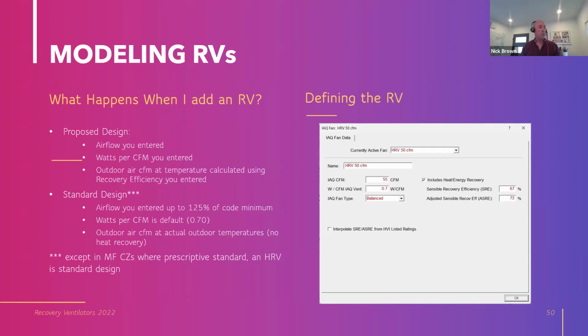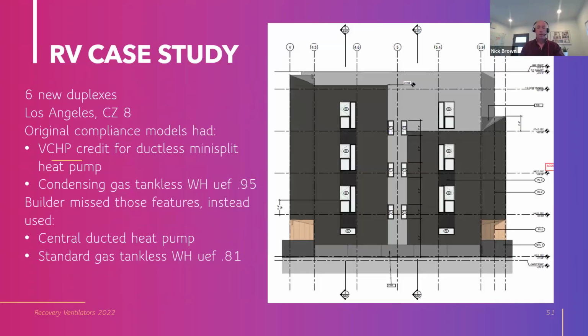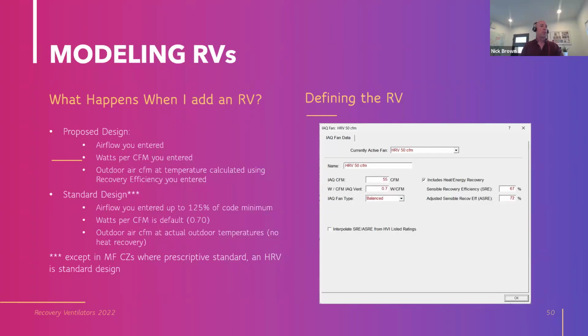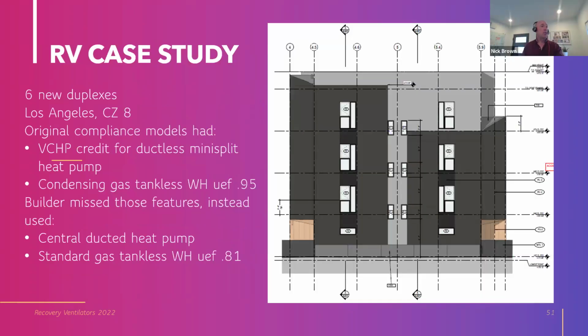Watts per CFM is default 0.7. And the outdoor air comes in with no heat recovery, so you're getting the whole benefit of that. And here you see that HRV that we specified: 55 CFM, 0.7 watts per CFM, balanced, 67% sensible, 72% adjusted sensible. As I understand it, the adjusted sensible takes into account the fan heat, whereas the sensible does not. Best place to look up these metrics is in the HVI database.